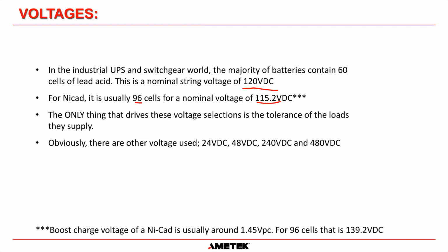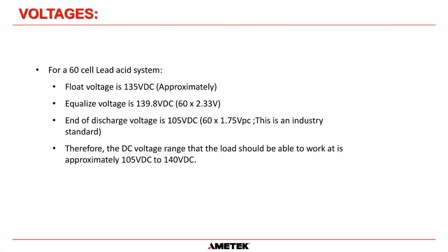And the reason why they don't have more cells, like 100 cells, to make it up to more like 120 volts, similar to the lead acid battery, is because the boost charge of a NiCad is usually around 1.45 volts per cell. And for 96 cells, that takes that voltage up to 139.2 volts. And we'll explain in the next few slides why we can't really go above that. So that is the nominal voltage of those systems.